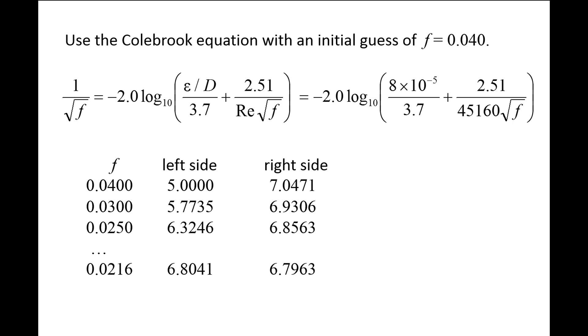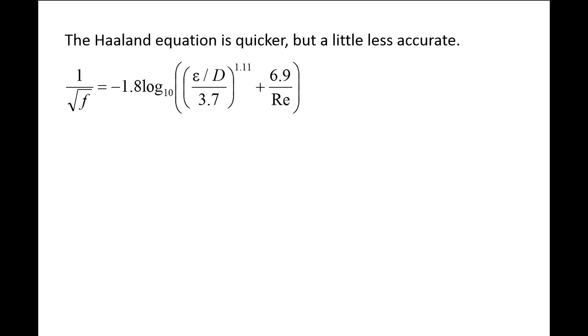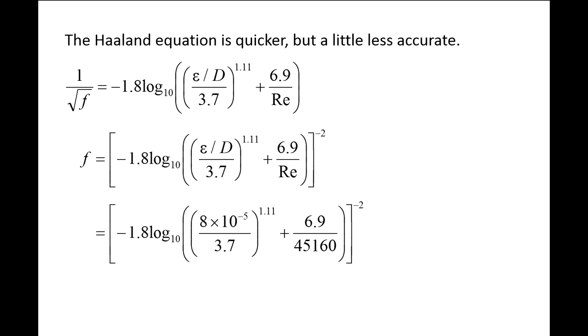For example, if we reduce the value of f to 0.0216, the left side and right side are almost equal and we are done. There is no point in finding more significant digits for f because the Colebrook equation is based on experiments that had limited accuracy. We also could have used the Haaland equation to determine the friction factor much quicker. We solve for f by raising the entire equation to the negative 2 power. Plugging in the values for the relative roughness and Reynolds number, we obtain a friction factor of 0.0214. Although the Colebrook equation is more accurate, the result from the Haaland equation differs by less than 1%. In practice, this small difference is usually negligible compared to other uncertainties in the problem, such as the uncertainty in the absolute roughness value and in the values of the minor loss coefficients.